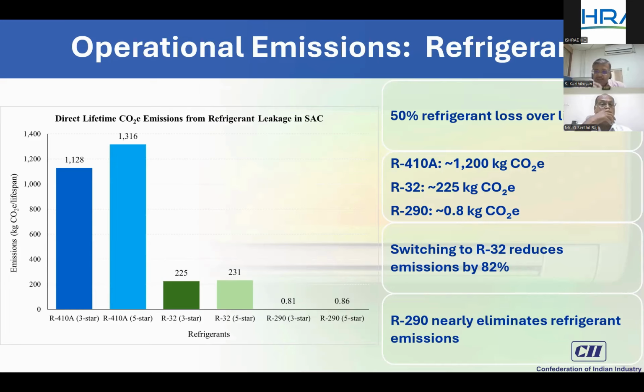On the other hand, R32, if you look at it, is equivalent to about 225 kg of CO2. On the natural refrigerant like R290, it is hardly about 0.8 kg of CO2. So the selection of a refrigerant makes a large difference in terms of the carbon emission.